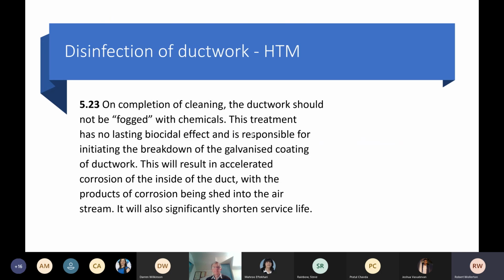So an interesting one here, disinfection of ductwork. People often say to us, can you disinfect the system when you've completed? Are you going to fog the system? Under the HTM 03-01 guidance, fogging, disinfection of ductwork is not recommended. Introducing moisture to the ductwork can cause the galvanized coating on the ductwork to be affected, and we understand that introducing moisture to the system can also cause proliferation of bacteria. So you should only disinfect ductwork if it's clean and if there's a need to do it, as in there's been a risk identified that there is a need to disinfect that system. So just to clarify, disinfection of ductwork is not recommended.